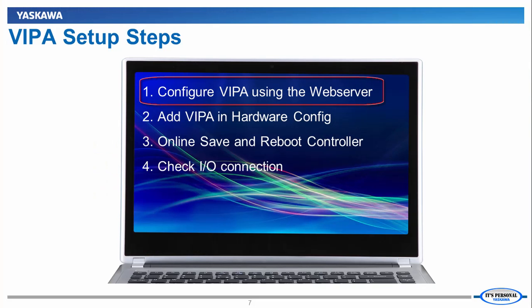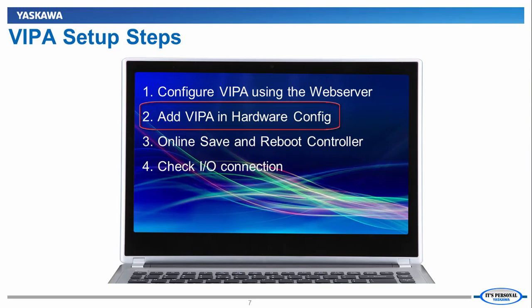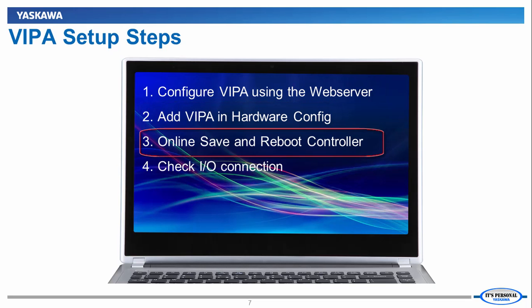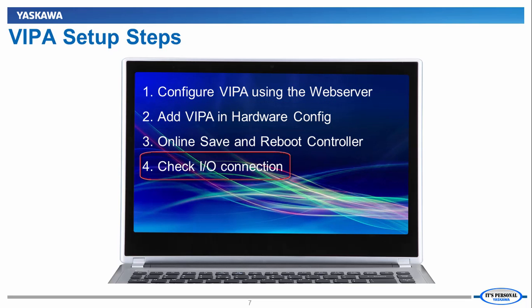First, I will configure the VIPA SLIO system using the web server. Then I will open MotionWorks IEC3 hardware configuration and add the VIPA system as an Ethernet IP adapter. And then I will perform an online save and reboot. After this is done, the IO connections can then be checked.